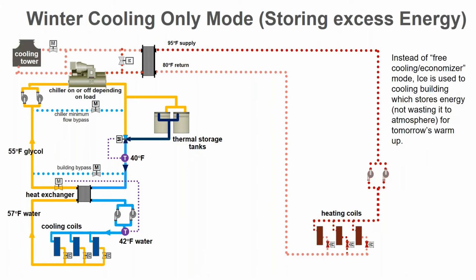Winter cooling mode, well, that's pretty easy. You've got storage tanks that are now devoid of energy, so they're ice, they're in the solid mode. And so now the chiller is not running. We're just going to circulate liquid through the tanks, just as you would be cooling the core in the summer, or the building, wherever it is in the building. You're going to be running the pumps and just taking the energy out of the building and putting it into the tanks and starting to charge up the tanks with energy.